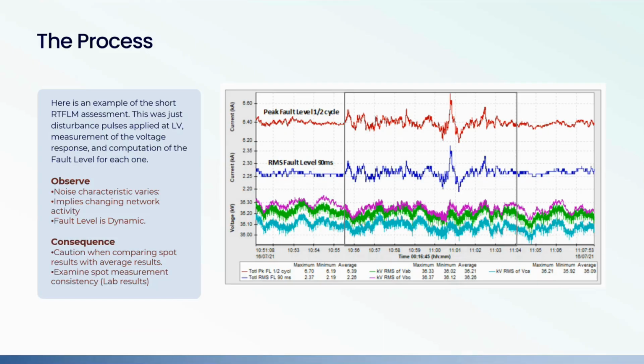If you just move to the next slide. So this is an example of some of the assessment waveforms that were obtained. So just the disturbance pulses applied, the LV, and the measurement of the voltage response and the computation of the fault level for each one. So you've got the peak fault level traces at the top and the RMS fault level underneath. There's some observations around how noise affects the measurements and the implications in terms of change in network activity. But again, and as we see on some of my slides later from our deployments, we can see fault level as a dynamic value rather than a static value. And just move to the next slide.